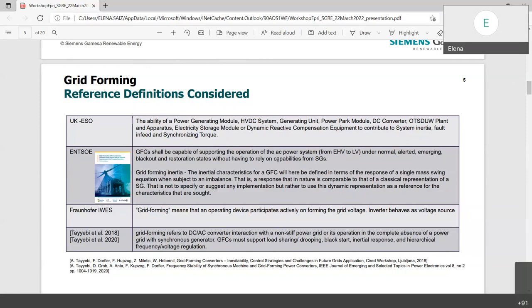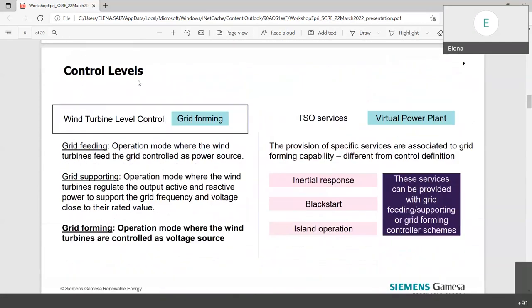This slide is to outline that there are still many different definitions of grid forming, and that we should be talking about the performance that we want instead of the specific controller that we need. In this sense, we present here this slide, in which we clearly identify two levels. On one hand, we have the control level, and we are going to talk about grid feeding, grid supporting, and grid forming. Grid feeding is our actual situation, in which our wind turbine operates as a current source, and in grid forming we are going to behave as a voltage source behind an impedance.